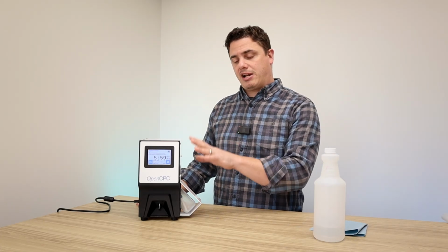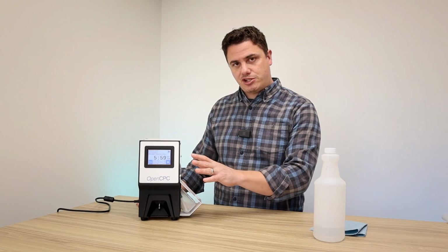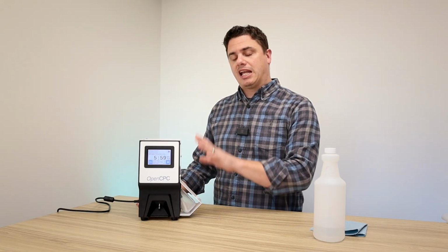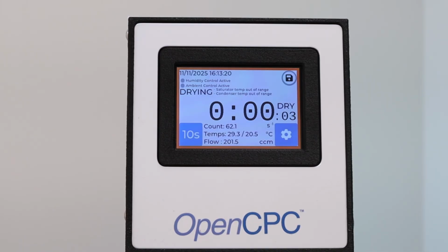The device will operate at an elevated flow rate and temperature for 6 hours. Upon completion, it will turn off all the pumps and the temperature controllers to be in a steady state mode, ready for power down and shipping. All right, dry mode is now complete. We're now able to power down the CPC. To do that, we will use the switch to power off the device and unplug it from the power supply.